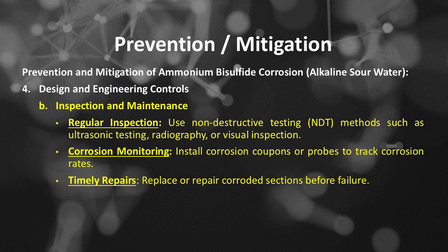Design and engineering controls, number B, is inspection and maintenance. Regular inspection uses non-destructive testing, or NDT, methods such as ultrasonic testing, radiography, or visual inspection. For corrosion monitoring, install corrosion coupons or probes to track corrosion rates. Make timely repairs: replace or repair corroded sections before failure.